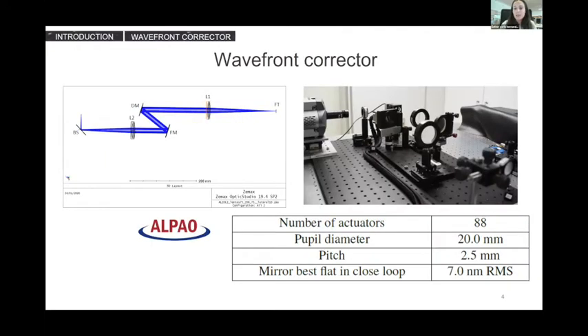I will start with the wavefront corrector. A design as simple as possible using commercial achromatic doublet, the collimating lens images the entrance pupil on the DM, and then a second focus lens. The relationship between the focal length is one-to-one to avoid generating magnification. In the near future, this compact design allows to incorporate a tip-tilt mirror along the optical path. In this case, we have reused the DM from the previous project. It is from Alpao with 88 actuators.